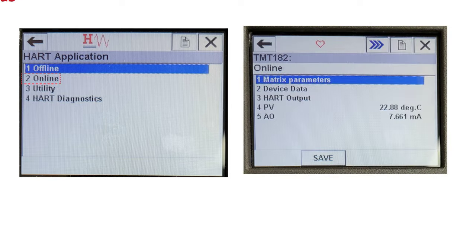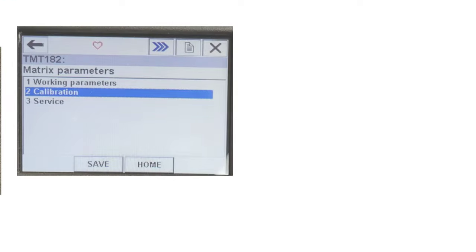When you go online, you can find 5 different options such as Matrix Parameters, Device Data, HART Output, PV, and Analog Output. Select Matrix Parameters and press the RH button to enter that menu. Then select the Calibration option and press the RH button to enter the Calibration menu.